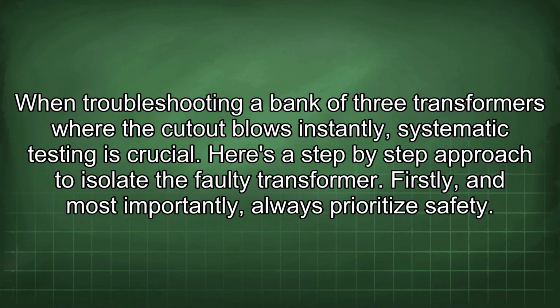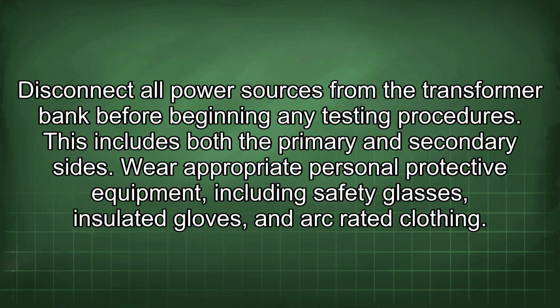When troubleshooting a bank of 3 transformers where the cutout blows instantly, systematic testing is crucial. Here's a step-by-step approach to isolate the faulty transformer. Firstly, and most importantly, always prioritize safety. Disconnect all power sources from the transformer bank before beginning any testing procedures. This includes both the primary and secondary sides.